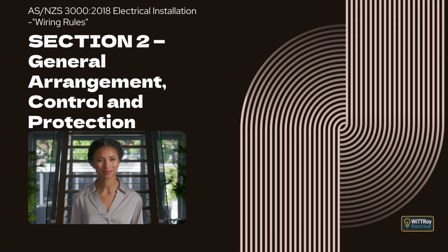The level of fault current considered here goes up to the level of an arcing fault current, which is generally taken as between 30% and 60% of the prospective short-circuit current. To meet this rule, discrimination must be provided between the protective devices so that faults on any one safety service, or faults on the general installation, do not take out the supply to the other safety services. The standard gives an example in Figure 2.13 to show how the devices should be arranged.